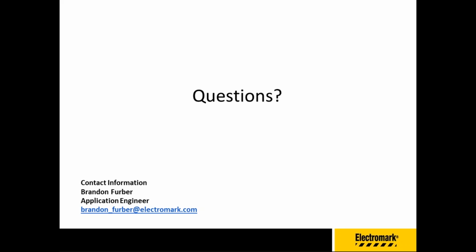The first question: are there any other backgrounds besides black and white that I can use for my signs, like yellow, orange, etc.? Good question, but it goes directly back to one of our earlier slides where we talked about the use of color in the ANSI Z535 standard. The colors are reserved for the header word. For the background where the word message is, it can be either black text on a white background or white text on a black background only. You're not allowed to use any other color schemes for the word message panel area of the sign or label.